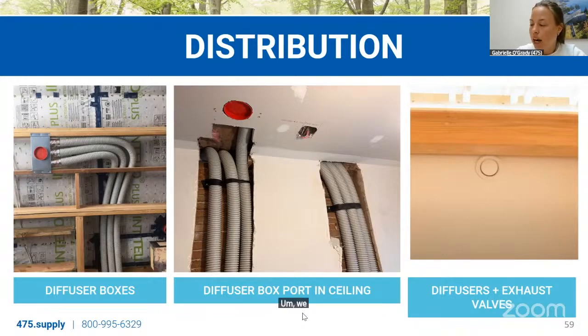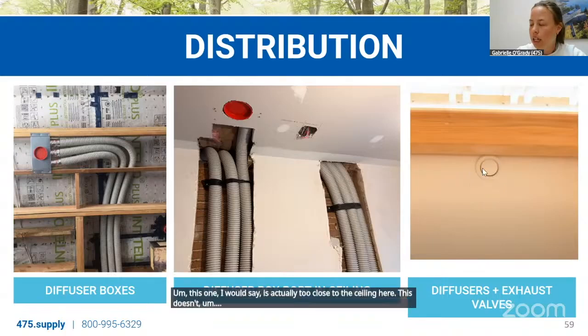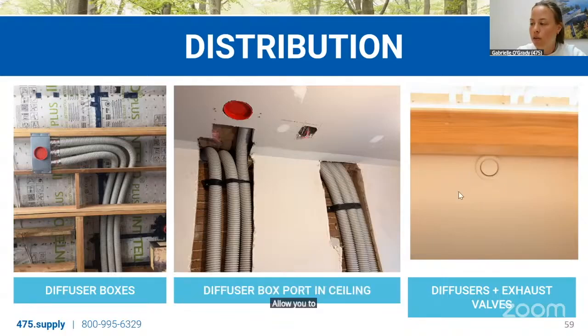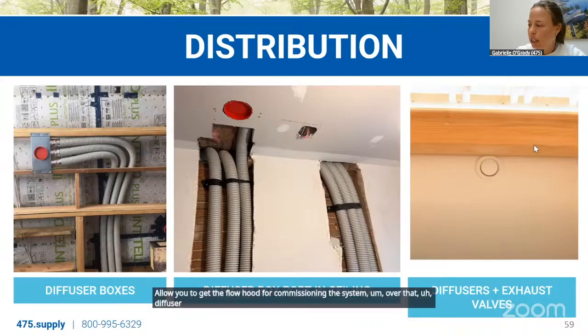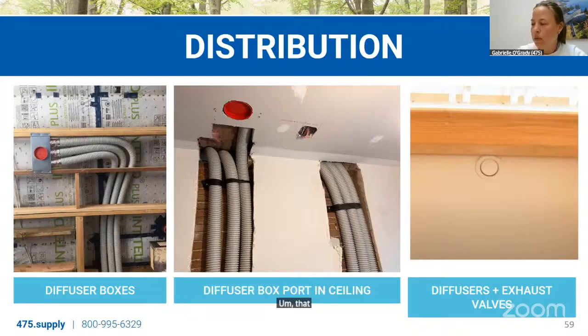We have round wall and ceiling diffusers. This one I would say is actually too close to the ceiling here. This doesn't allow you to get the flow hood for commissioning the system over that diffuser. So it's recommended to have the diffusers 1 foot away from corners, ceilings, cabinetry, 1 foot clearance on all sides.